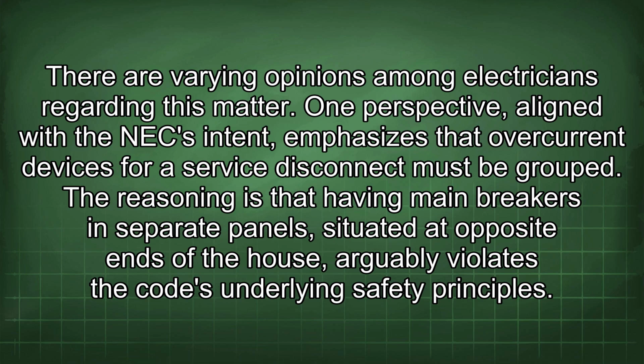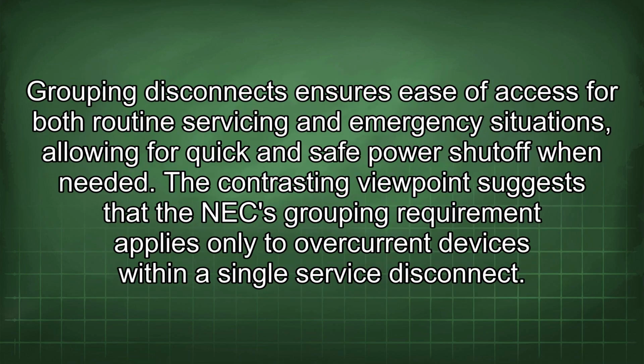One perspective, aligned with the NEC intent, emphasizes that overcurrent devices for a service disconnect must be grouped. The reasoning is that having main breakers in separate panels, situated at opposite ends of the house, arguably violates the code's underlying safety principles. Grouping disconnects ensures ease of access for both routine servicing and emergency situations, allowing for quick and safe power shut-off when needed.